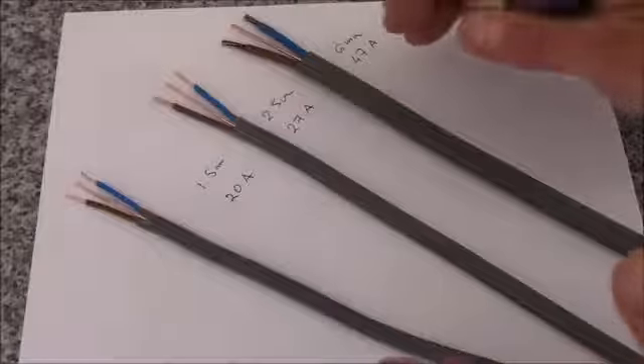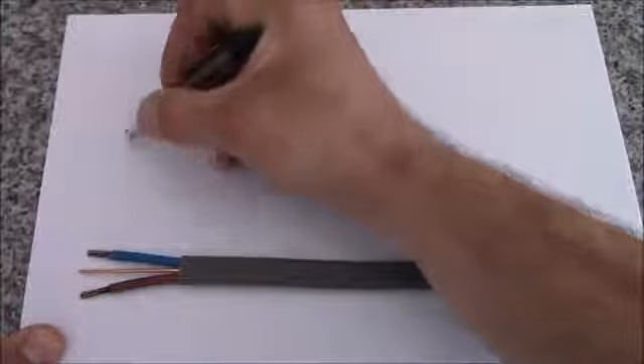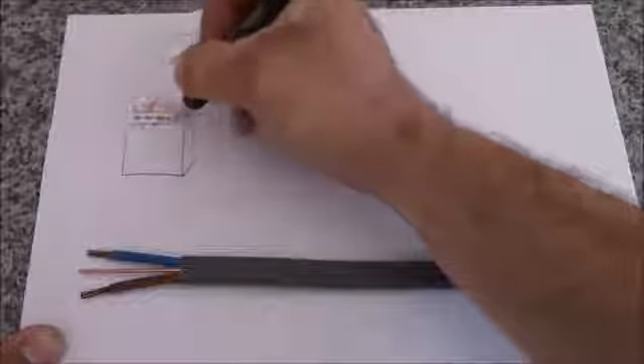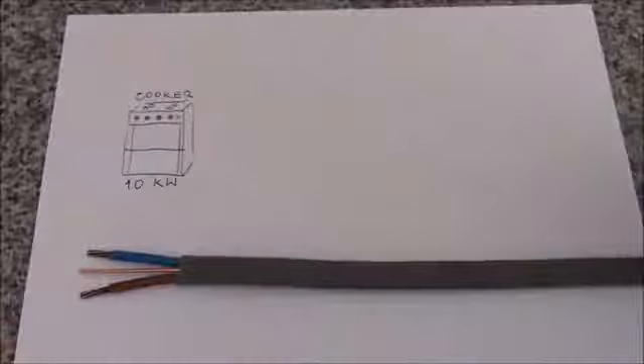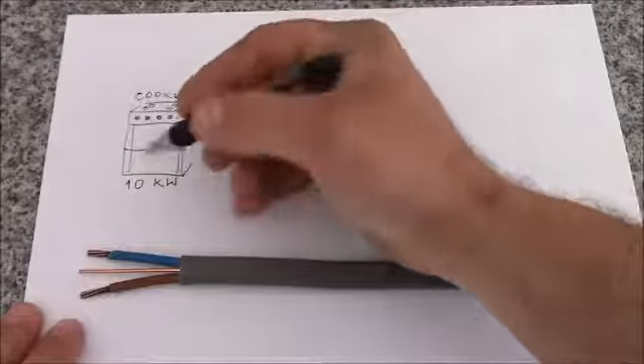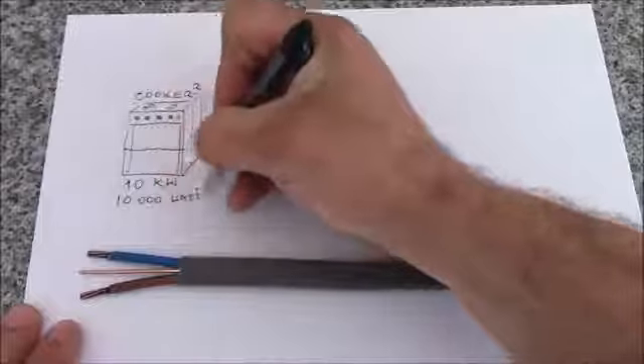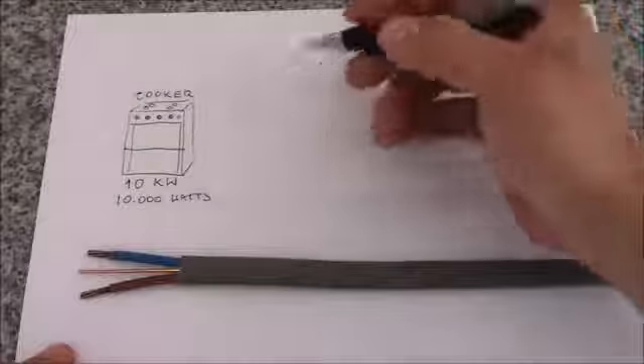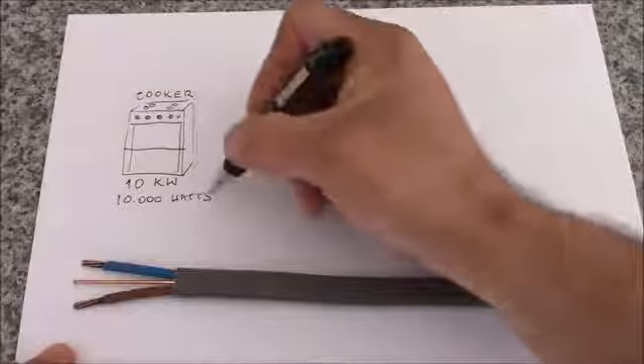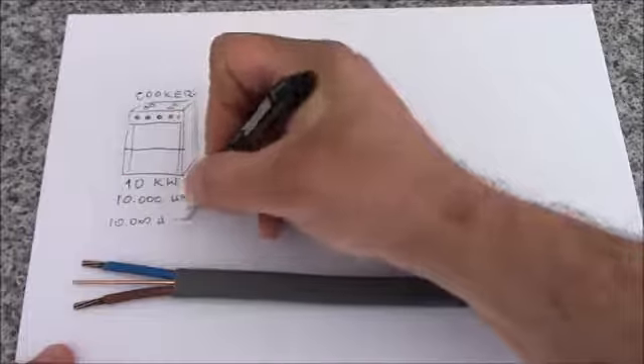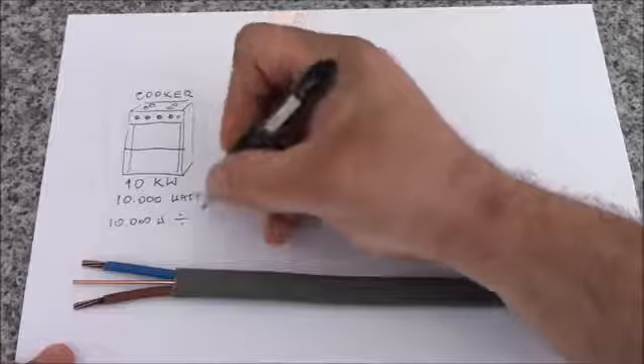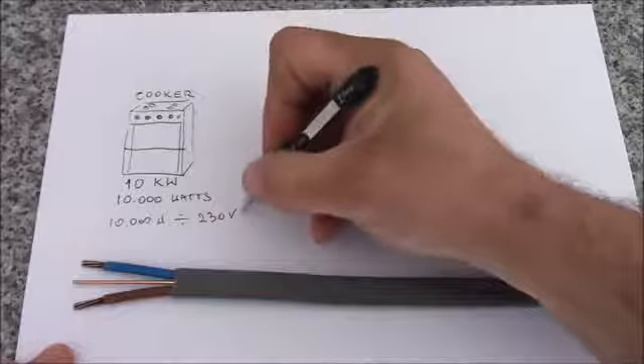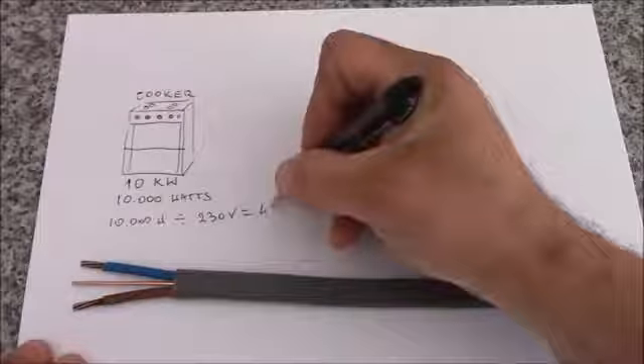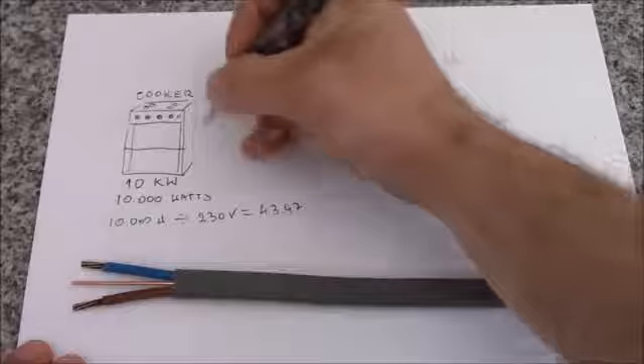So now I'd like to show you how to calculate the cable size for the design circuit. Let's say we have a cooker, and the power of the cooker is 10 kilowatt. 10 kilowatt is 10,000 watts. To calculate the cable size we need amps, not watts, so we need to convert the watts into amps. So 10,000 watts you have to divide by the voltage, which is in the UK 230 volts, and this gives us about 43.47. So let's say 44 amps. That's our cooker.